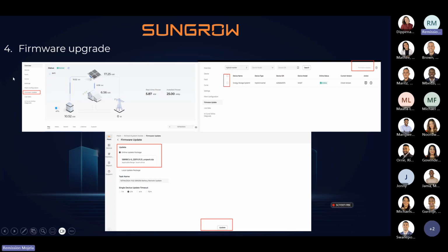Depending on which device you have, the firmware is always available on the iSolar Cloud Remote Maintenance, the latest one. What I also recommend is, unless told by Sungrow technical support or Sungrow applications, which is Leonard, you don't need to change the firmware as long as the plant is working correctly. Unless there's a feature that you require and we ask you to update the firmware, then update the firmware. Or you have an issue that you can't clear and we recommend that you update the firmware, then you update the firmware. You don't need to continuously update the firmware as long as the plant is working correctly, or Sungrow suggests you do so.